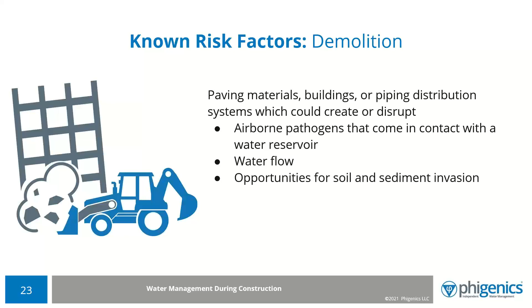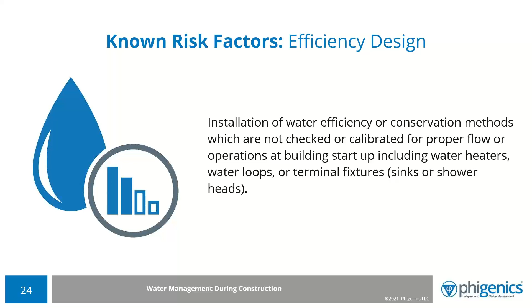Efficiency design. As much as our AEC professionals may be designing to the building code or these rating systems, nothing wrong with that, but how are you making sure these systems come online properly? How do they have proper flow? Is it appropriate for the building type, the user type? How is this impacting water heating, water loops, and terminal fixtures? I find that people just simply assign these to the project without having a more robust discussion about how that's going to impact the building occupant and water safety. So you don't want to install all these things, have them not work, and then have a disease case or an outbreak and have them all removed.